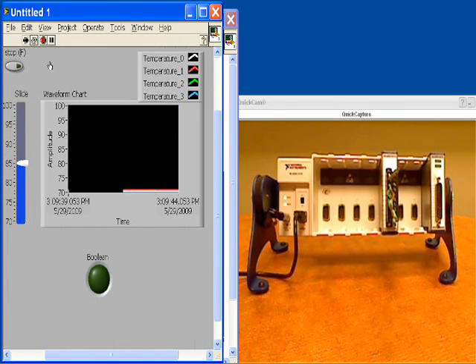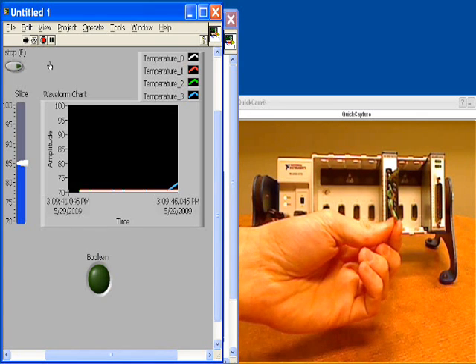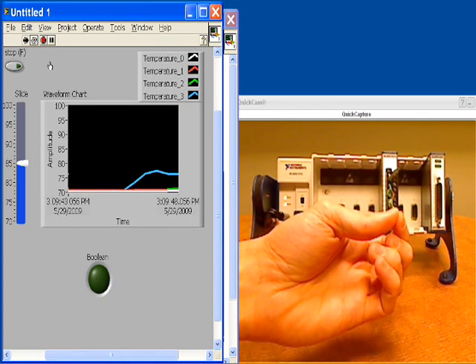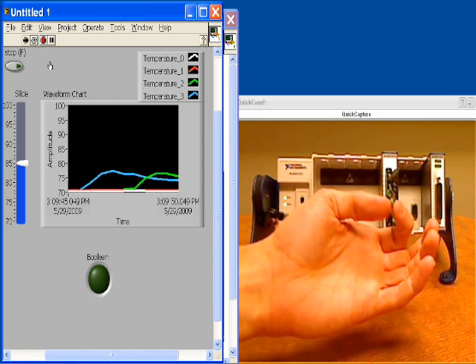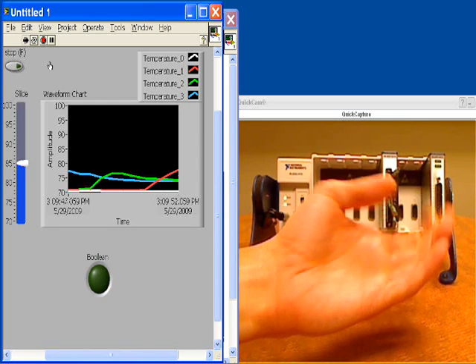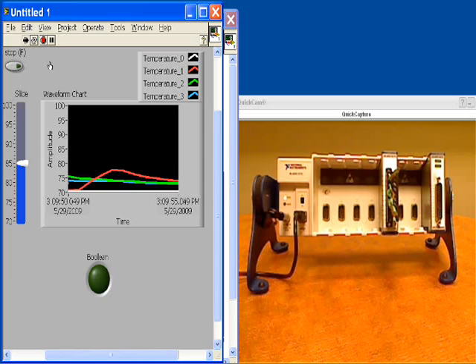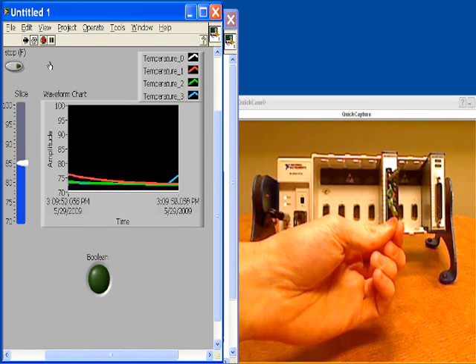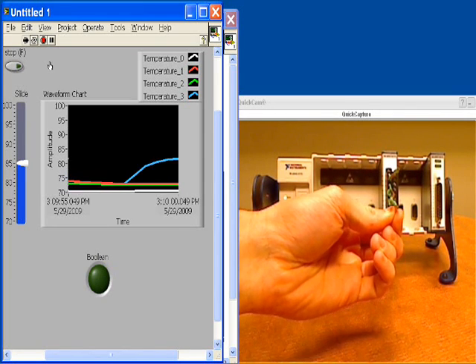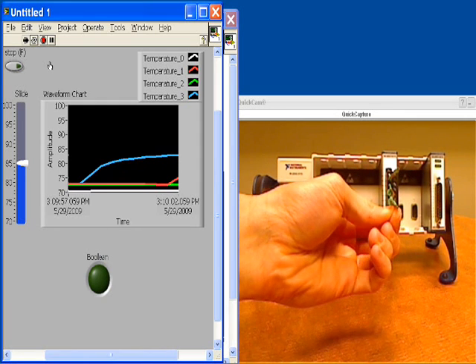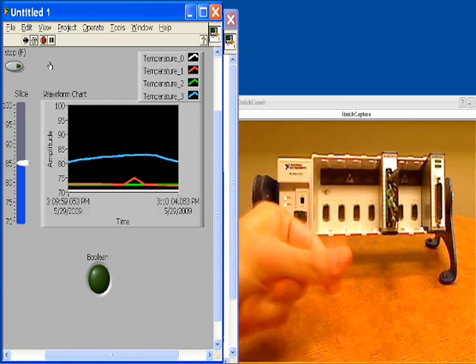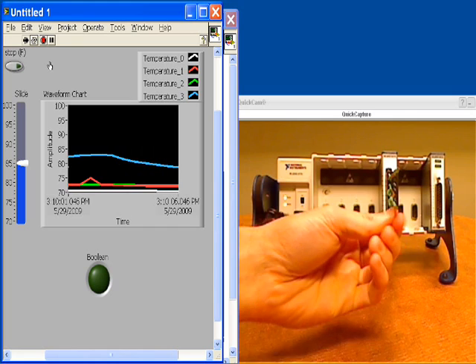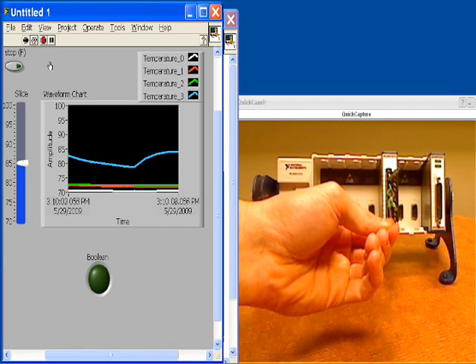And you can see my temperature coming in from the bottom. And as I place my fingers on the channels, you can see that I've got different colors for each thermocouple. You can also see that even though the set point is at 85, if I were to select channel 3 and take it over 85, I'm still not going to trigger the alarm because we've selected channel 0 as the alarm function.